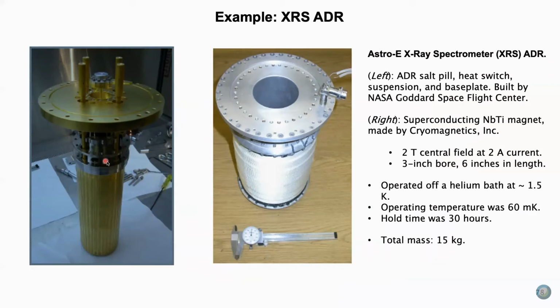This is XRS, the Astro-E X-ray spectrometer ADR. This is the salt pill with wiring here, and a thermal bus. And this fits inside the bore of a superconducting magnet. The salt pill, heat switch and suspension were built by Goddard. The superconducting magnet is a niobium titanium magnet built by Cryomagnetics. It has a 2 Tesla central field at 2 amps, 3-inch bore, 6 inches in length.